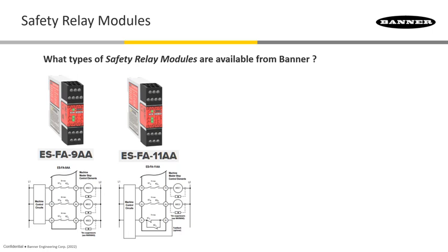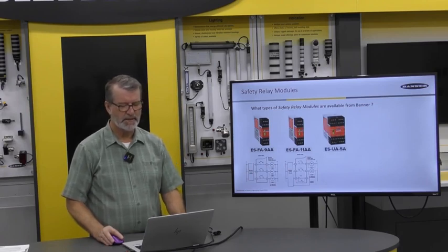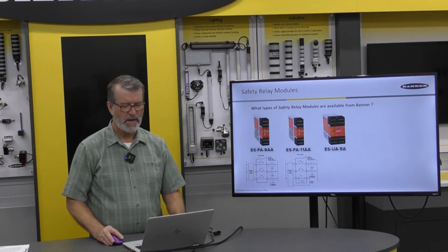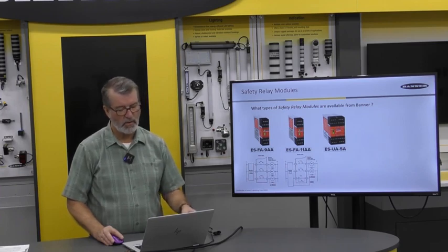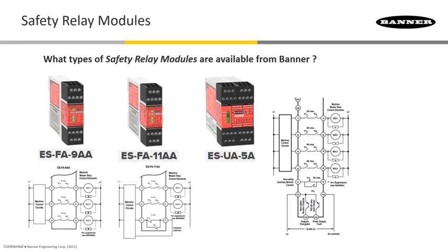Other safety modules used for this purpose include the ES-UA-5A, with power options including 115 volts AC or 12 volts to 24 volts DC. It has four normally open safety output paths rated at 6 amps, plus three non-safety auxiliary outputs, so that you can take annunciation through to a PLC or whatever the case may be.